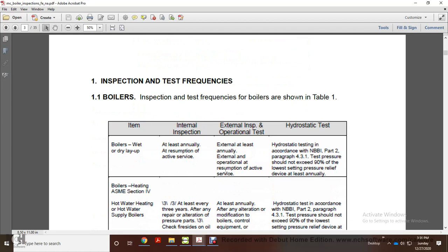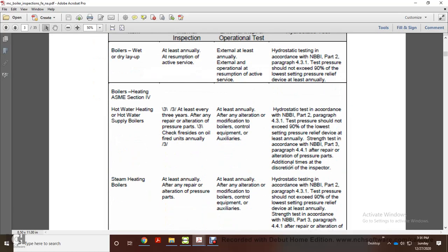Alright, your inspection and testing frequencies for boilers are shown in Table 1. The boilers are wet and dry lay-up: inspected annually at resumption of active service, external annually, external operation, and at resumption of active service. Hydrostatic testing is according to NBBI Part 2, paragraph 4.3.1. Test pressure should not exceed 90% of the lowest setting of the pressure relief device, at least annually.